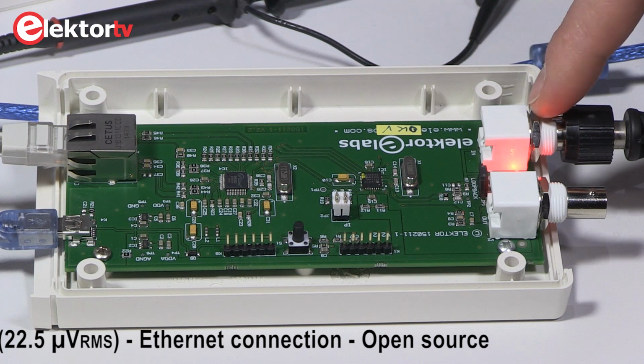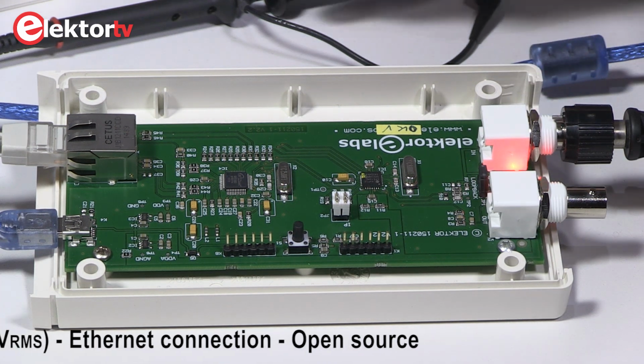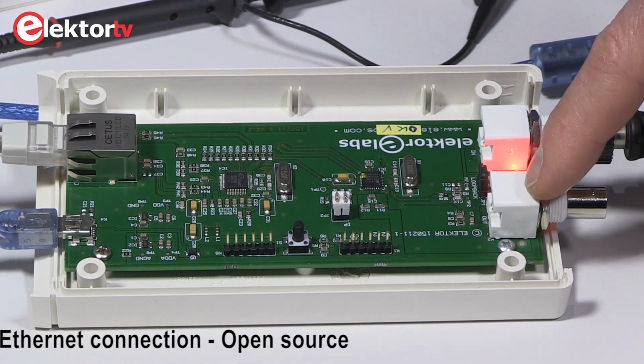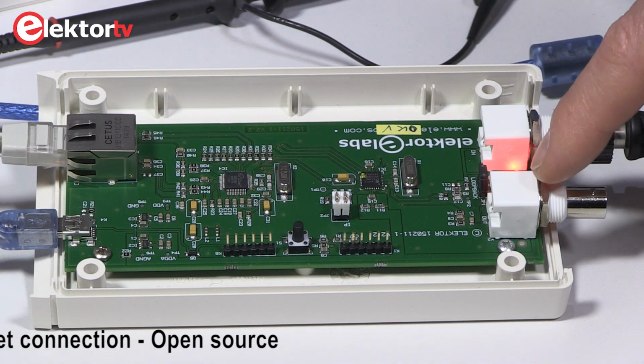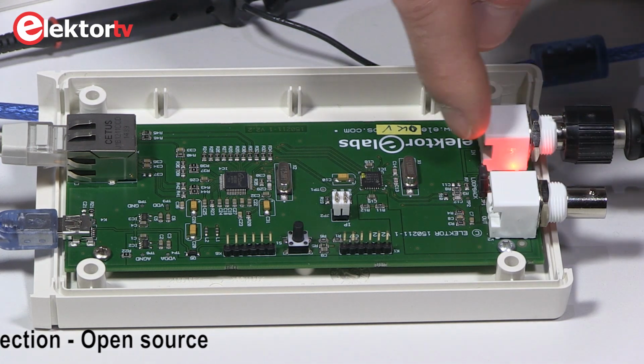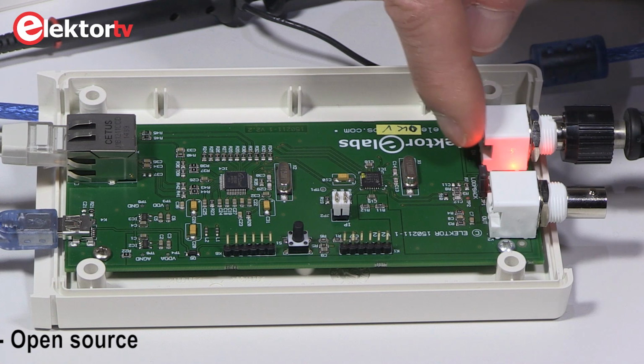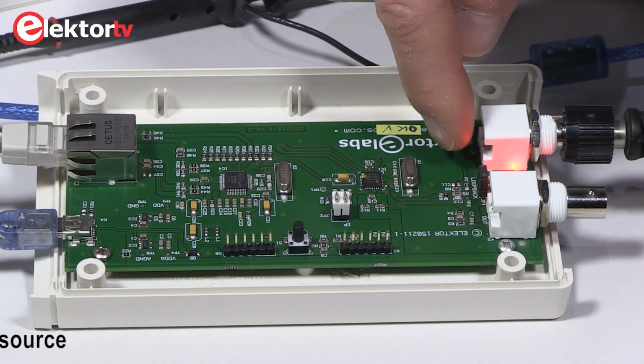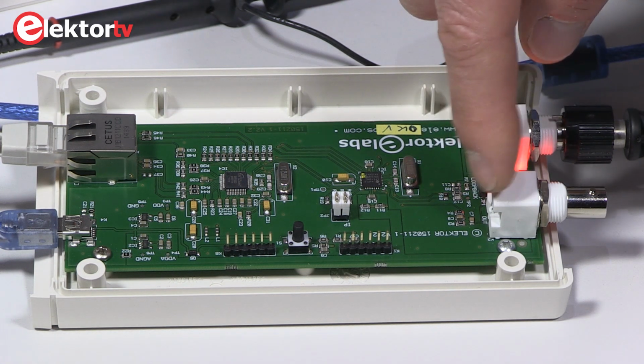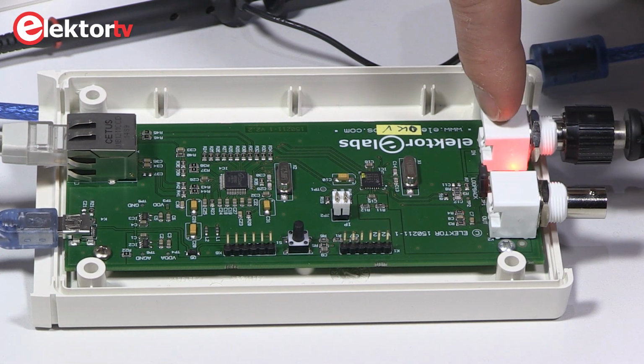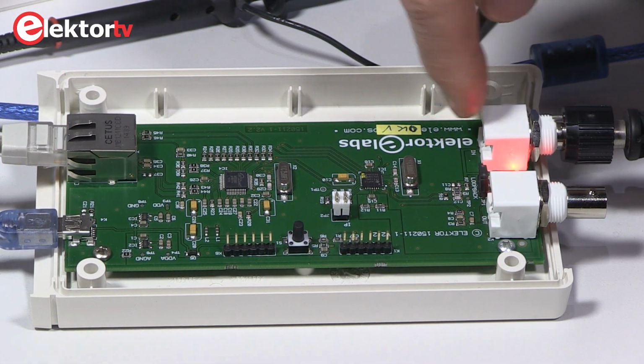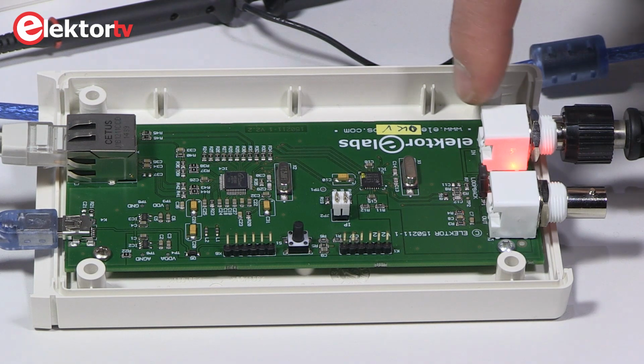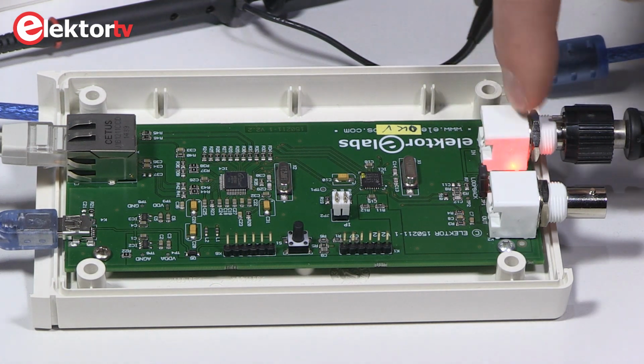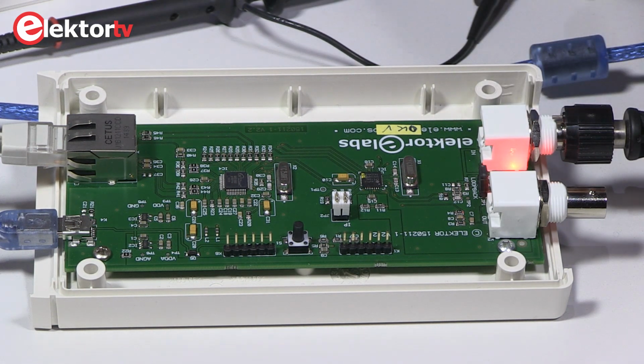One is the input connector for your probe, and one is the output connector for the signal generator. In between there is a jumper, which selects loopback mode or normal mode. In loopback mode, the output of the signal generator is looped directly into the input, and so you can exercise the hardware without connecting to any real electronics.